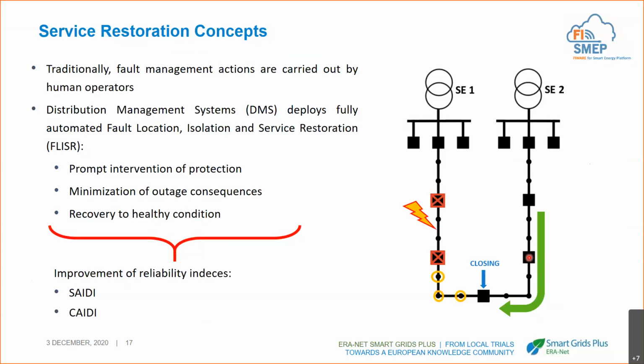feeder. And this operation traditionally was carried out by the operators, who were driving directly to the fault location, identifying the position, and manually opening or closing the switches. But what we can do nowadays is to automate the whole process with the distribution management system. And in this way, we can carry it out in a minimum time with the so-called fault location, isolation, and service restoration, which synthesizes all the phases of this process.